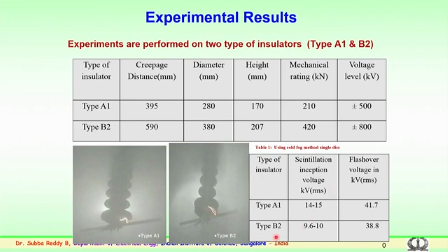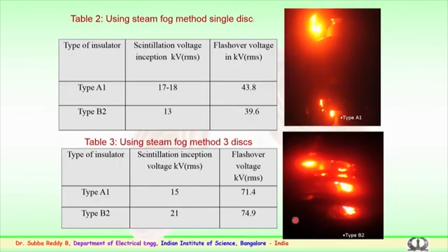Similarly, for the B type insulator, the inception of scintillations was noticed at 10 kilovolts itself, and the flashover was 38. You can very clearly see that even though the creepage distance is very high, the inception of scintillation takes place early. So, the design aspect is very important. The inception of scintillation has to be limited or arrested, so that further discharge activity does not come across.